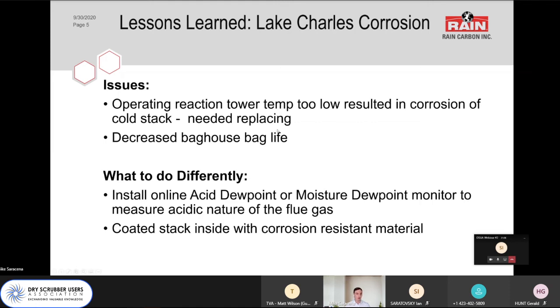So, as I said, we root cause this by saying that the flue gas temperature was too low, so we increased it, and then we had to incrementally decrease it and optimize it as we saw a massive increase in lime use due to this increase of temperature. So what would we do next time? I would definitely recommend installing either an online acid dew point monitor or a moisture dew point monitor to measure the acidic nature of the flue gas. They're really not very expensive, and they would have saved us many hundreds of thousands to millions of dollars in corrosion costs. We also coated the inside of our cold stack with a corrosion-resistant material. Again, there's some question as to how well these materials work. I think the proper way to address this problem is to have some feedback on how corrosive the flue gas is via a monitor designed to do that.